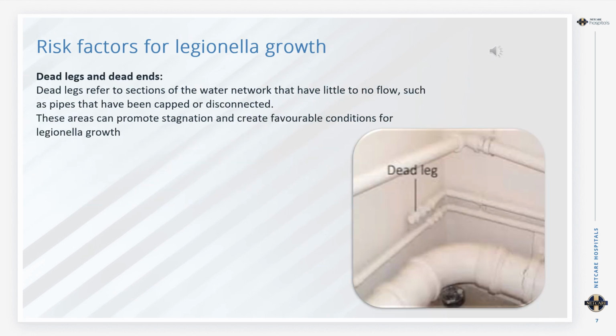The next risk factor is dead legs and dead ends. Dead legs refer to sections of the water network that have little to no flow, such as pipes that have been capped or disconnected. These areas can promote stagnation and create favorable conditions for Legionella growth.